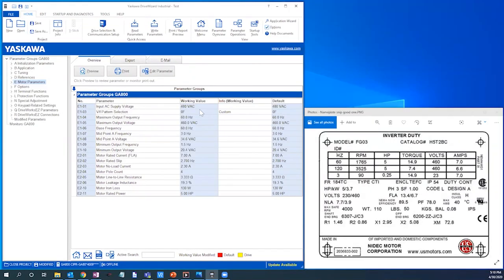Finally, let's verify our motor parameters. We already have our desired voltage of 480 volts AC pre-populated. Now let's enter the motor rated FLA being 6.7 amps for our example and save the working value.